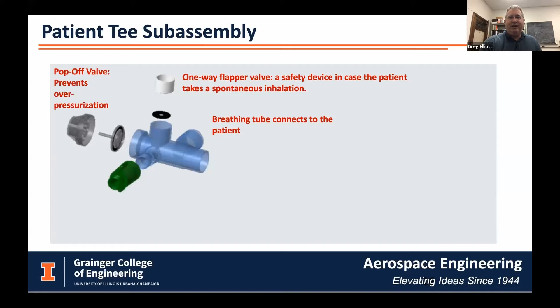There's a flapper valve in there so that if they do have spontaneous inhalation, it will open up and allow them to do that. Also, there's a pop-off valve that prevents overpressurization, so that if something was wrong in the system and there was too much oxygen pressure, it wouldn't overpressurize the lungs.